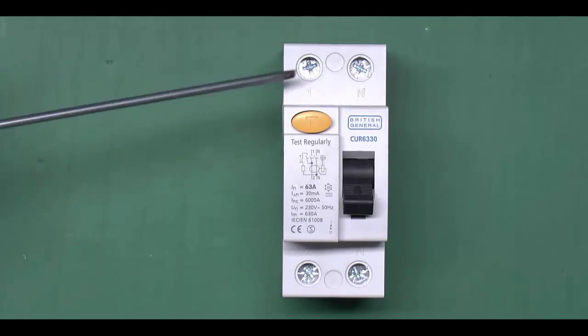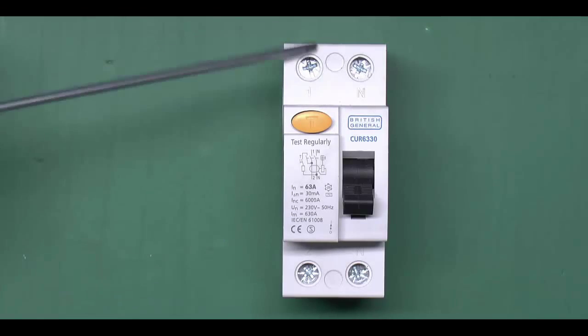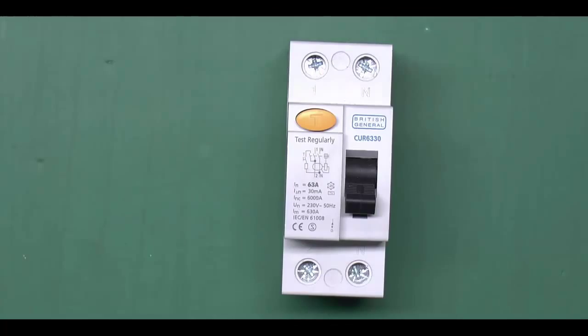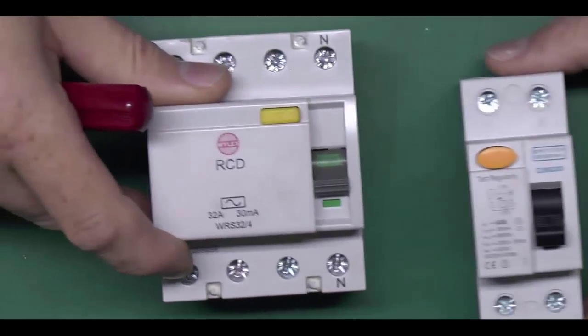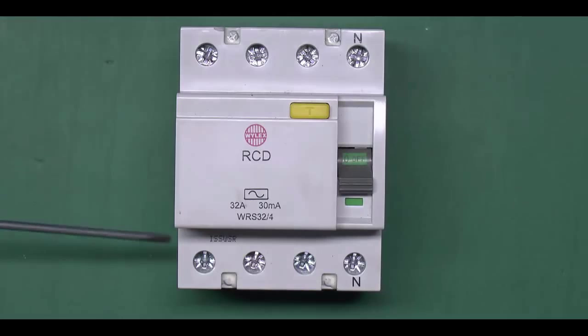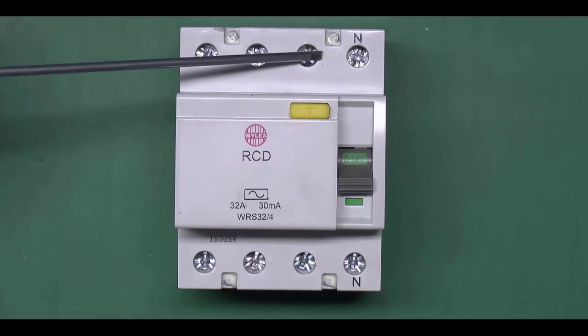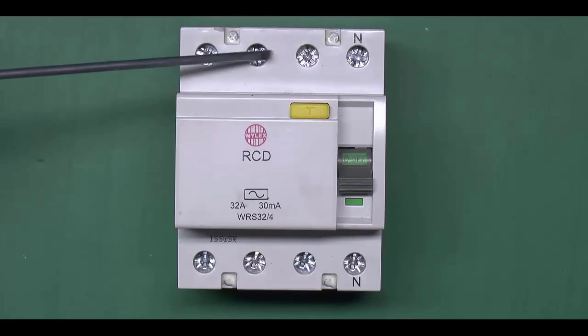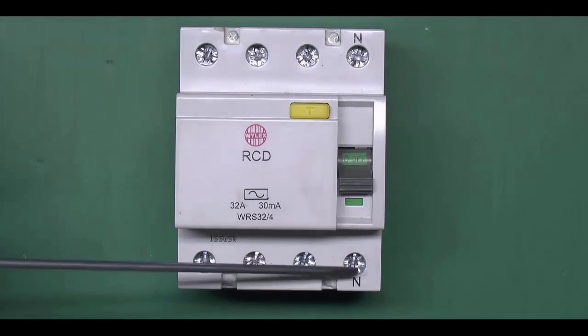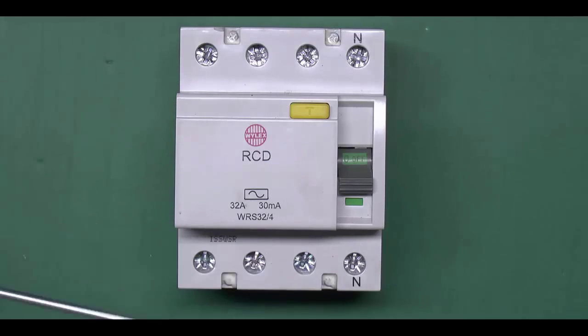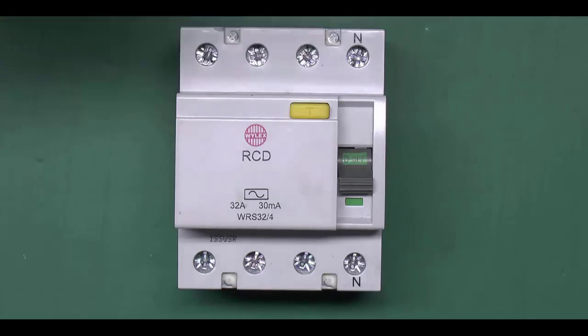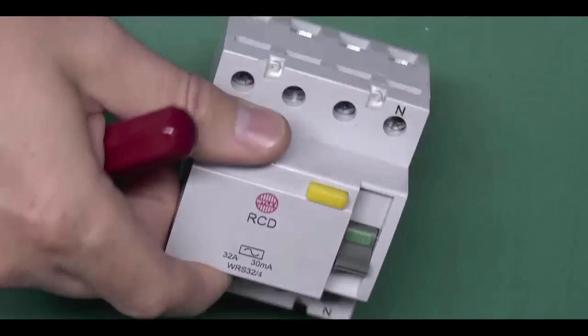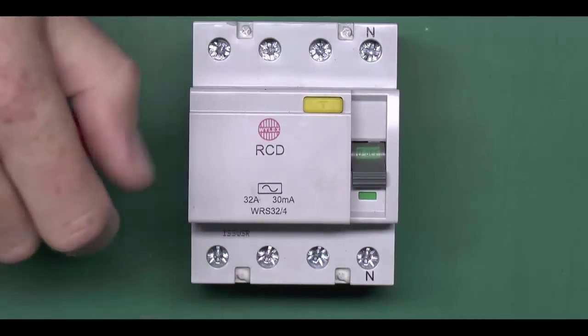Now this is a single phase device, it's just got the single line on this side of the neutral here. They are also available in a three-phase variety. This is a Wylex model, and again the similar principle applies, except in this case you've got the 3 line inputs here and the 3 line outputs, and again the neutral over that side. So in this case it's 3 phases coming in, 3 coming out, and of course the neutral for any current on the return. But again they work in exactly the same way. Same test button, and it's just obviously a physically larger device purely to accommodate the extra number of connections.